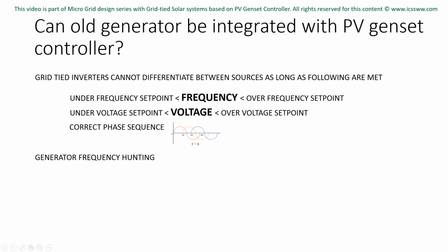If there is a problem with the generator, it keeps frequency hunting once load is added or removed. We highly recommend that before integration of the PV Genset controller, if the generator is frequency hunting, it must be fixed.